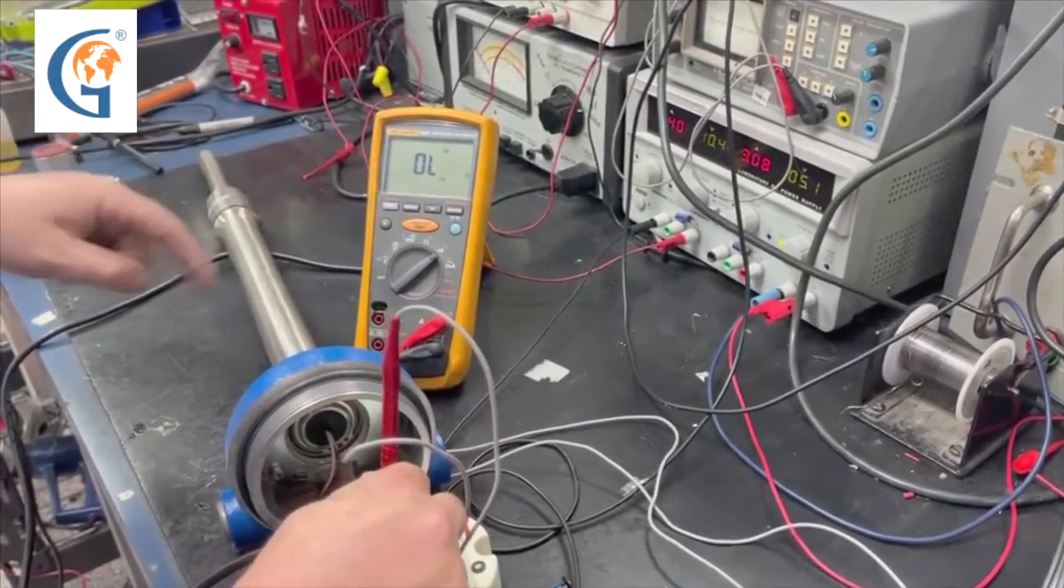Which is going to be monitored by our multimeter. Right now, we are seeing on the multimeter that we have an open line. So, that means that the relay is currently normally open, which we would expect when the rod would be within material.